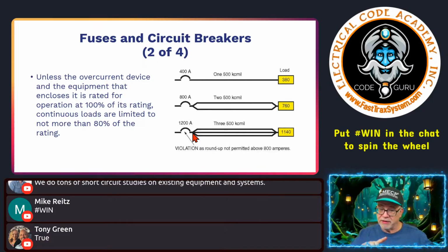Important that you know the difference. That's what's so important about the NEC, being able to realize what all you've got going on. You've got services with very limited protection on those service conductors. Only overload protection is available, not short circuit ground fault protection. And then, of course, once you get past the service, you get everything downstream, feeders and circuit breakers for branch circuits. Then we have to start worrying about all these additional rules, because we're only as good as that overcurrent protected device.